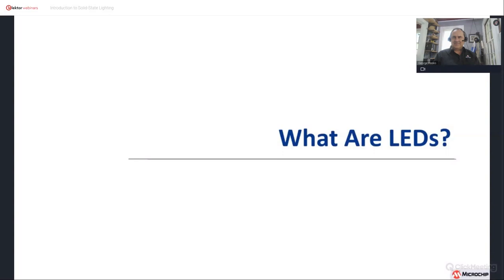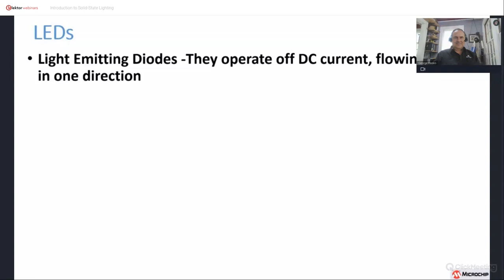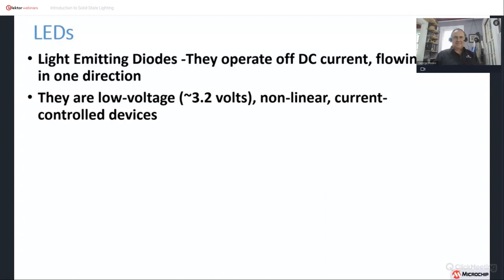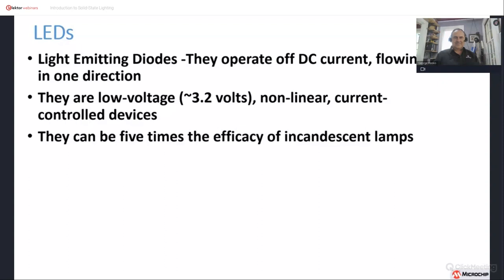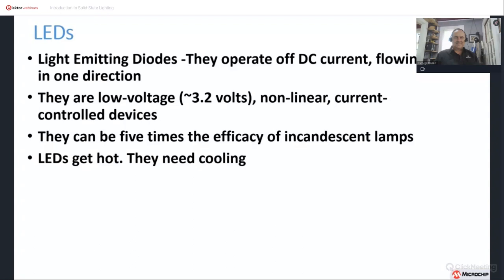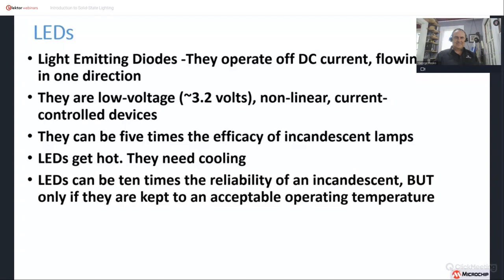Let's move forward with LEDs. What are LEDs? LEDs are 99% of solid state lighting. They are light emitting diodes, which means they operate off DC current flowing in one direction. They are low voltage devices — blue LEDs at the base of white LEDs have about 3 to 3.2 volts drop. They are non-linear, current-controlled devices. They can be 5 times the efficacy of incandescent lamps, which is why LED lighting has taken over. LEDs do get hot and need cooling; they can be 10 times more reliable than incandescent, but only if kept to an acceptable operating temperature.